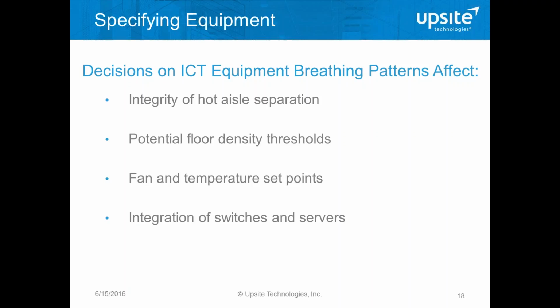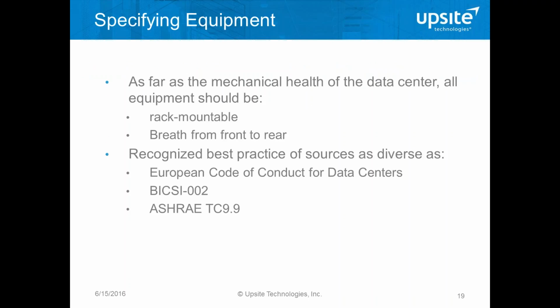It's also going to result in more fan energy being used to compensate for that mixing of return air, and it's going to result in higher chiller plant costs and reduced access to free cooling because of the lower set points required to compensate for that mixing. And we may also be looking at the way we integrate some of these side breathing switches in the data center is to take on the cost of separate rooms in which those switches are deployed.